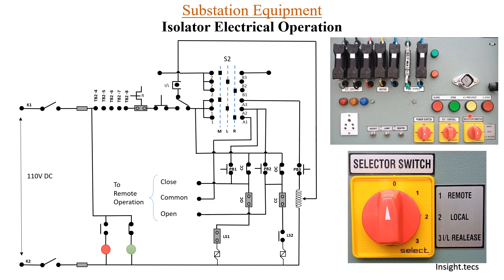In order to press the IL release and insert the key into the switch, you have to select the appropriate position on the selector switch. The selector switch must be at point number 3 — in that case only will you be able to press this push button and apply the key.